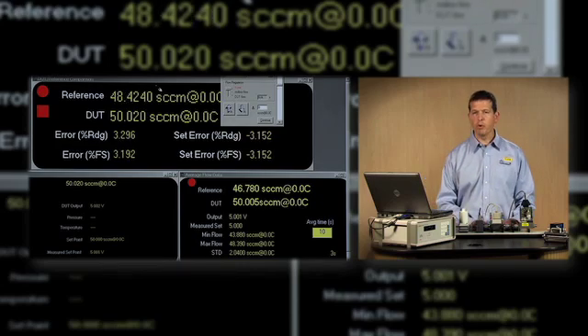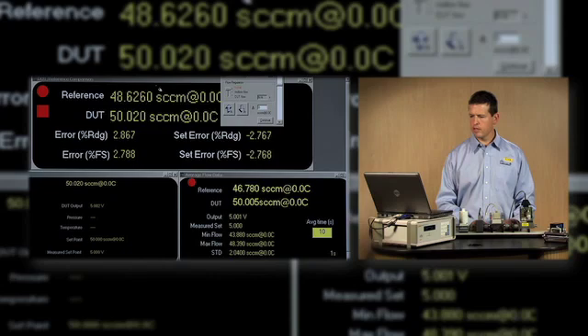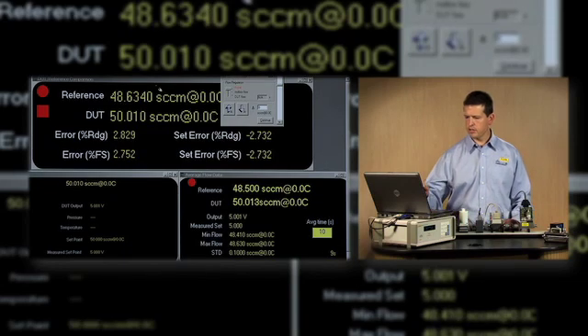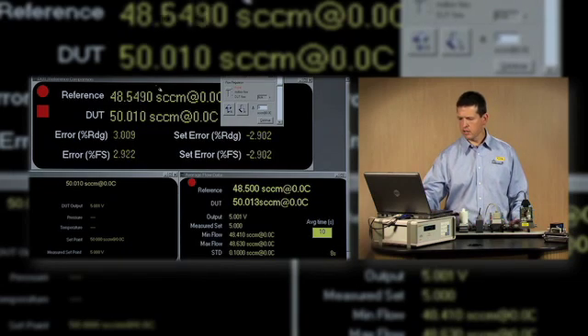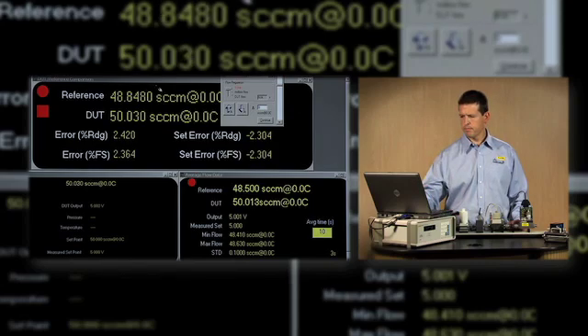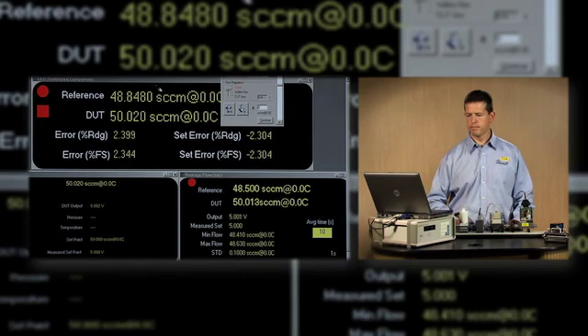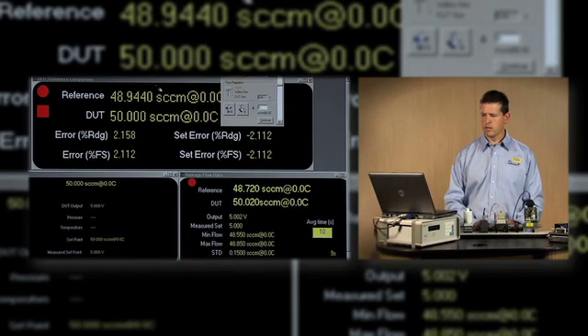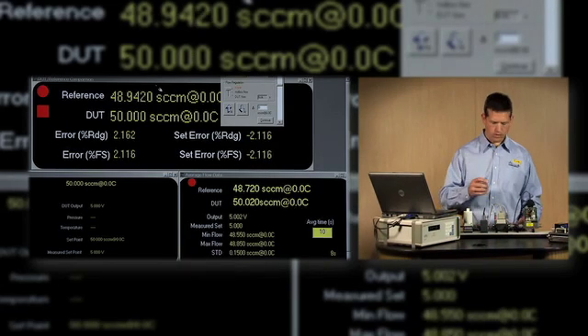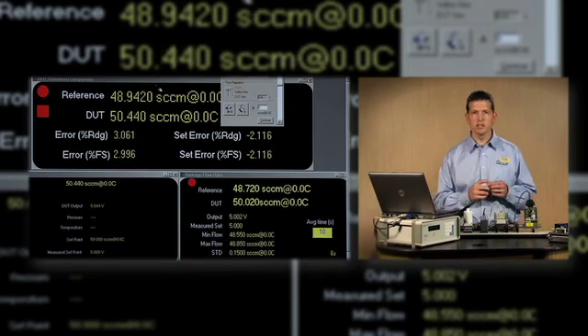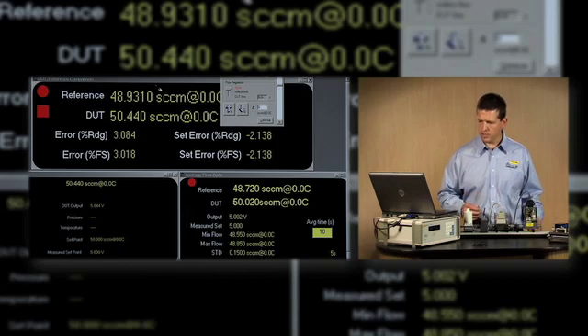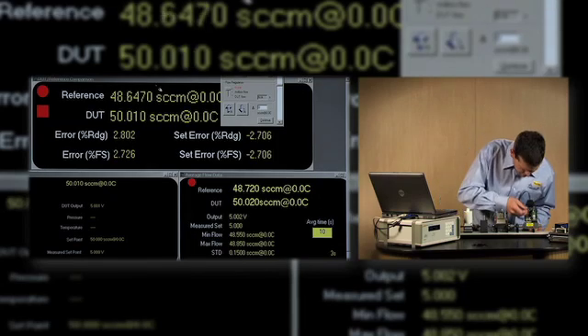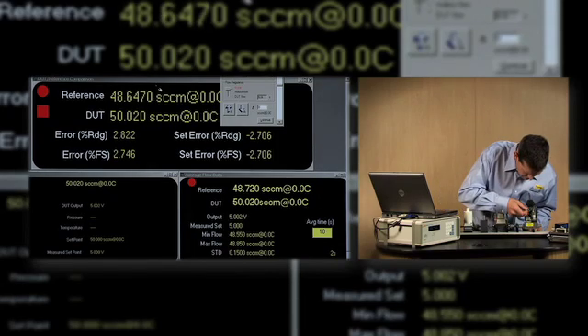The 100% point was actually well in tolerance on our test run as well. Okay, now we have some adjustments to make. Looks like our zero adjustment has had an influence on the 100% point.